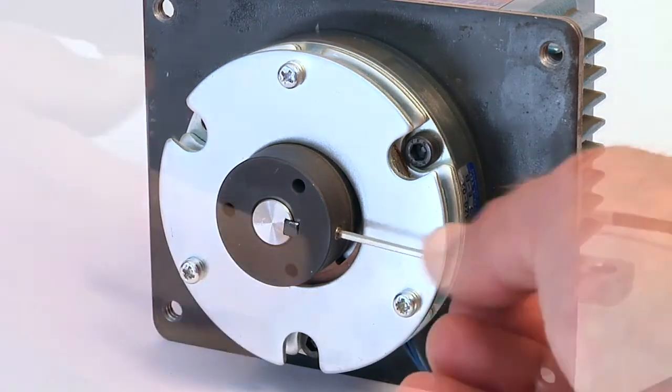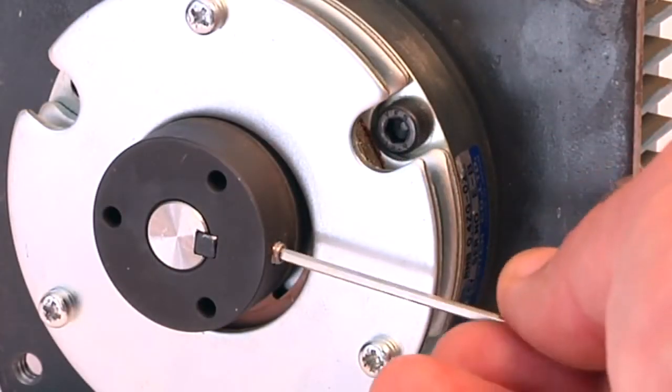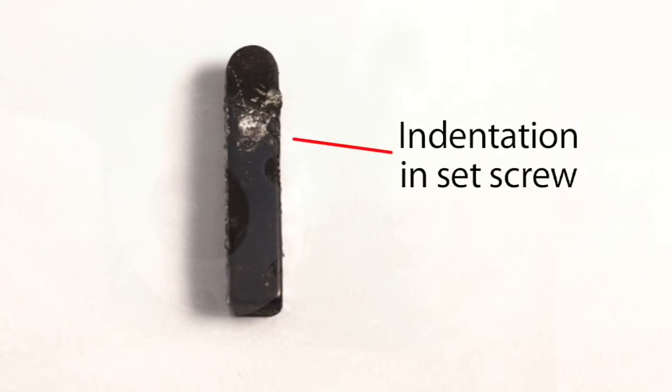If possible, try to slowly rotate the shaft. If any contact is noticed, release the set screw and try to reposition. To reposition the hub, the key may have to be moved if the set screw has caused an indentation.